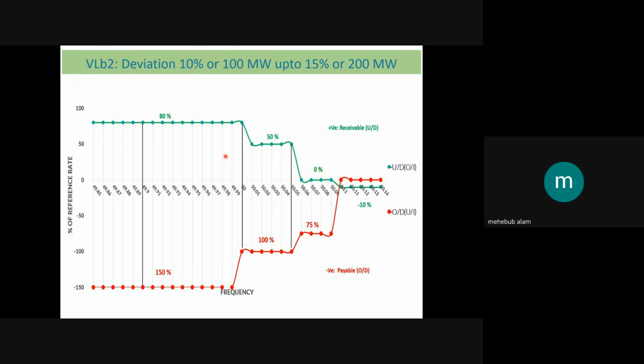Here also the main concept is the same: during low frequency, under generation will be avoided, because under generation will further cause grid instability. So they will be penalized at a rate of 150% of that rate for the low frequency range, 49.85 to 49.99. And beyond that, it will be 100% and 75% based on the frequency.